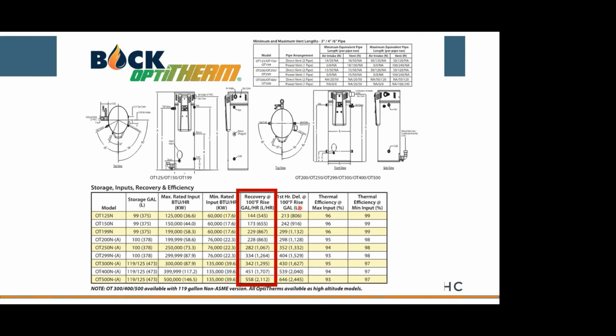You'll also notice there's a column next to that called first hour delivery. Well, what's the difference between these two? One's a little bit higher, and you might be tempted to use this. Be careful here. Recovery is the amount of water we can heat when the burner is firing, and within the first hour, or on an hourly basis. So 144 gallons every hour, and if the burner's firing for 8 hours, 10 hours, 24 hours, it doesn't matter. You're going to get 144 gallons every hour.